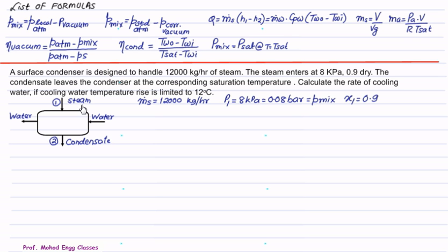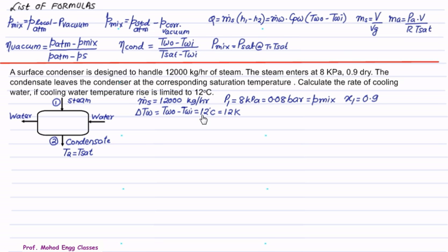In the schematic sketch, steam from the turbine enters at point 1 and leaves as condensate. Water enters at the inlet temperature and exits at the outlet temperature. The mass flow rate of steam is 12,000 kg per hour, pressure of steam is 8 kPa, and the dryness fraction is 0.9. The rise in temperature of water, TWO minus TWI, is limited to 12 degrees Celsius, which is the same as 12 Kelvin.